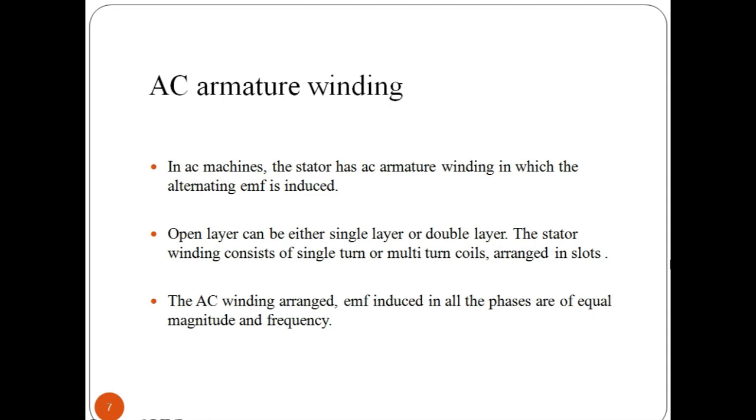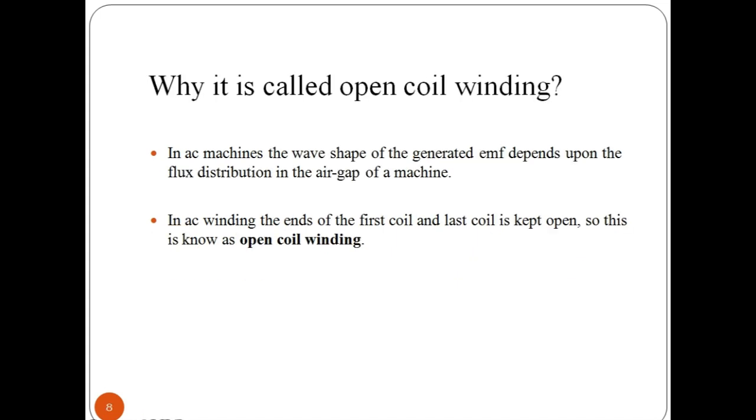Open layer can be either single layer or double. The stator winding consists of single turn or multi-turn coils arranged in slots and connected properly so as to obtain the required phase grouping. The AC winding must be properly arranged so that the EMF induced in all the phases are of equal magnitude and frequencies.